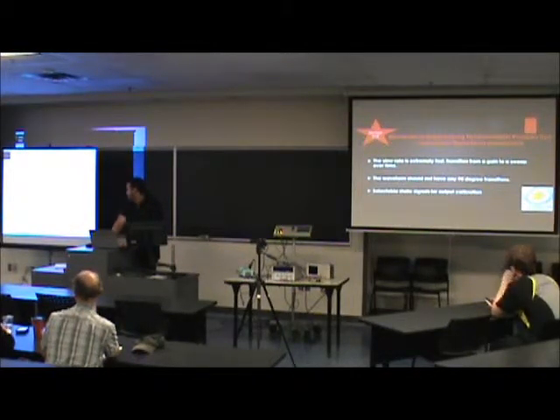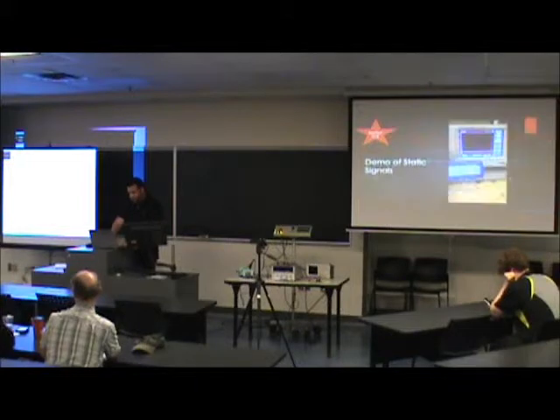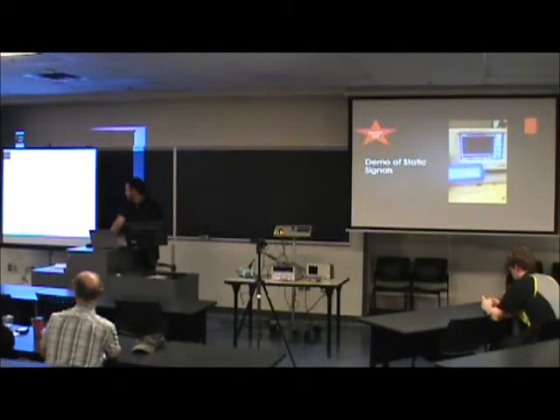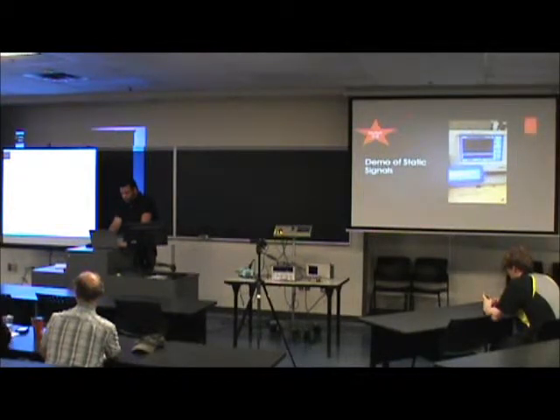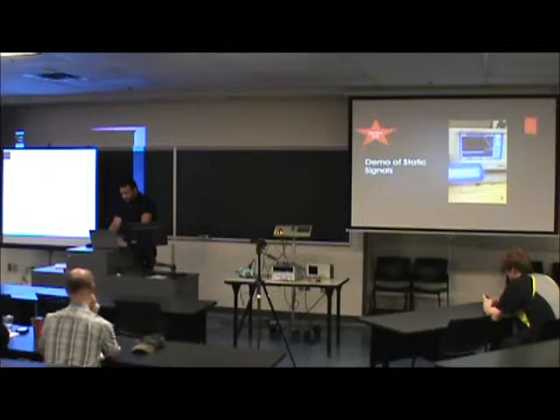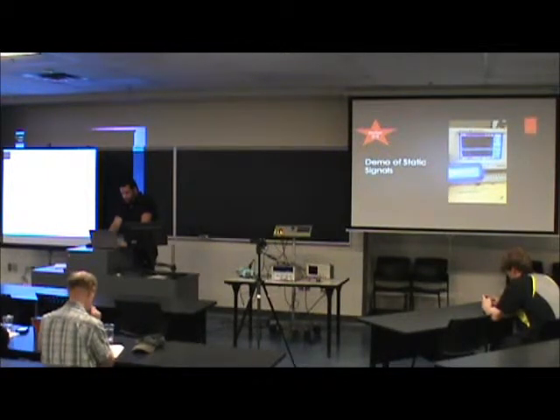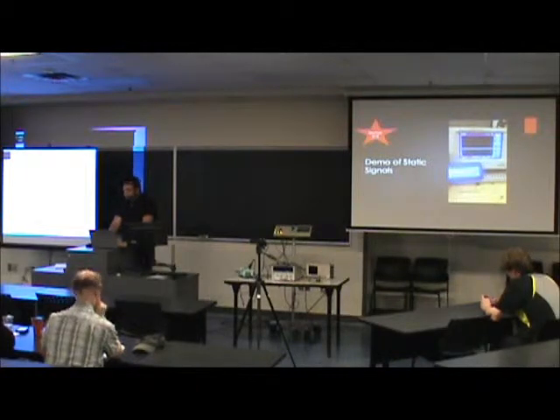Selectable static signals for output calibration. We're able to switch from 0, 40, 80, and 120, as seen in the demo next. So we can see on the screen it will show 0 millimeters of mercury as it reads. We're able to switch it now up to 40, and it's within the plus or minus 3 millimeters of mercury range. We can switch it up to 80, and the final is 120. As you can see.